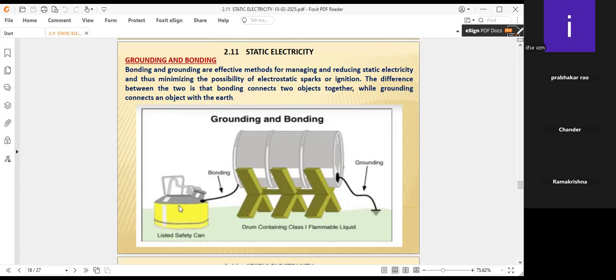So immediately bonding will be taken care of. It will balance the neutralization, balancing the positive charges and negative charges. Therefore, a flame or any spark will not be released in the flammable liquids. In clear terms, you can say bonding and grounding are effective methods for what? For managing and reducing static electricity, thereby minimizing the possibility of electrostatic sparks or ignition.